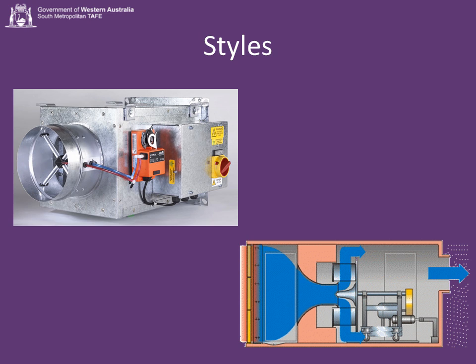The other type of VAV uses a plug which goes in and out of a seat in the duct. I'll get a pointer. So, there's the plug. It's a cone-shaped plug, and it moves left or right to insert or come out of the duct. It moves left or right because it's on a threaded shaft. The threaded shaft is moved in and out by an electric motor, and it moves the cone in or out of this piece of duct.